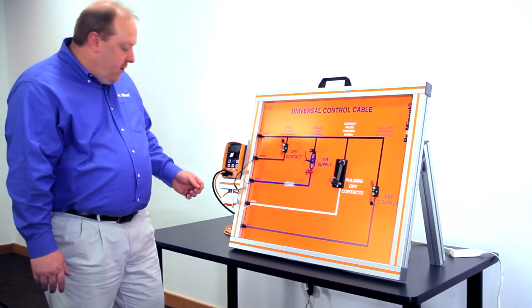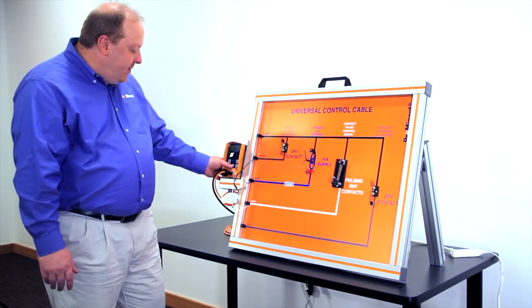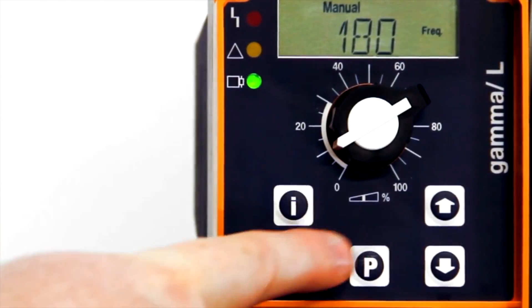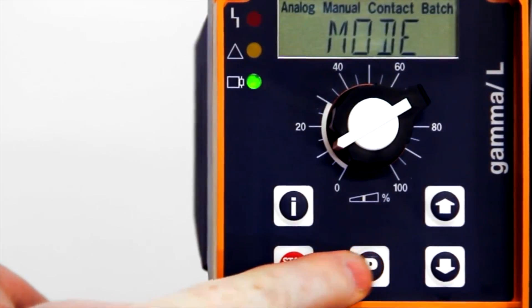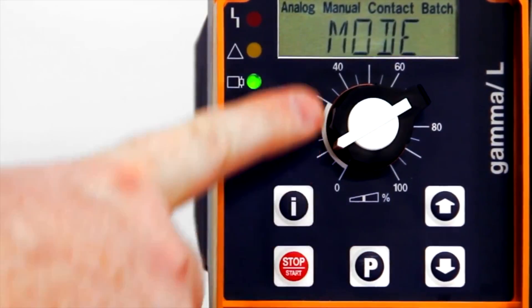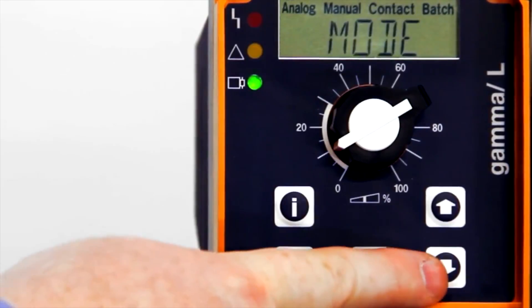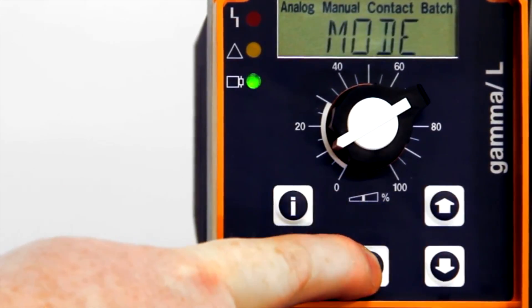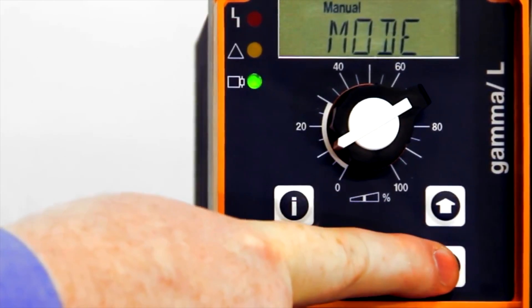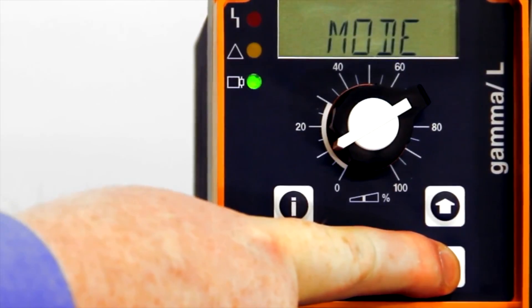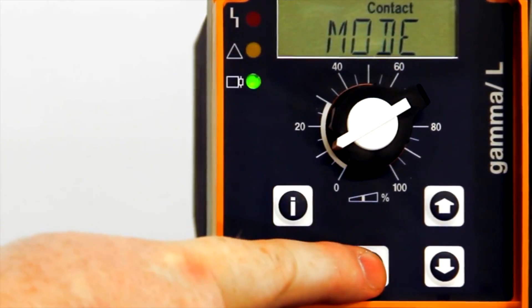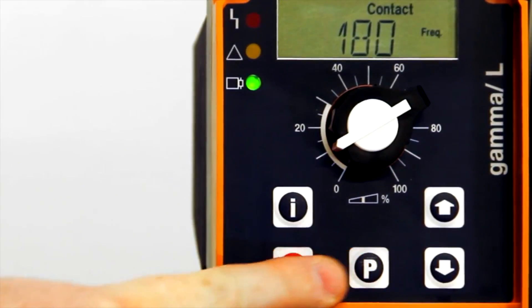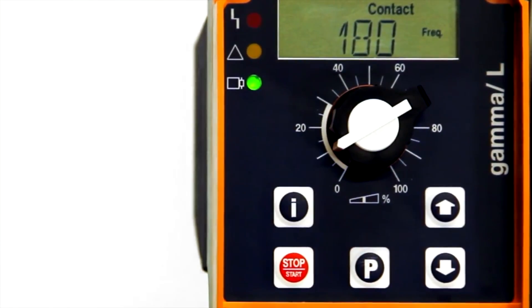The next mode of operation is the contact mode. To program the pump to contact mode, press and hold the P key, then look for the word mode with the up or down arrow buttons. Once mode is flashing, press the P key again quickly. Now scroll with the up or down arrow button until the word contact flashes. Press the P key once. Now the pump is in contact mode of operation.